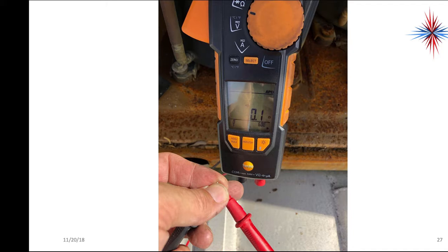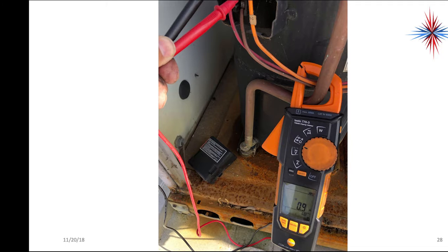Now, before I go on to do any resistance readings, especially on compressors, I do always self-check my meter. Put the two leads together, make sure I'm getting either 0 or as close to 0 as possible on ohms. It makes a difference. Start ohming compressor terminals. Verified that the other end is completely disconnected from everything on the contactors. It was. I chose to disconnect it at the contactor rather than here because the compressor terminals are screw-on terminals.